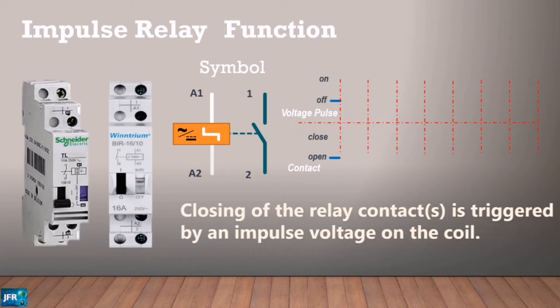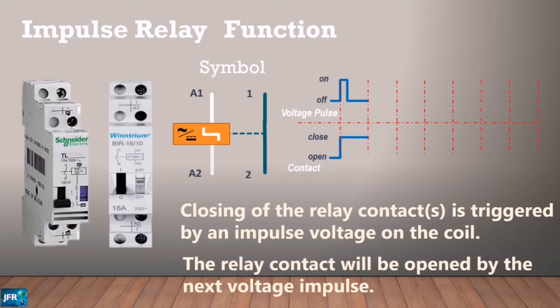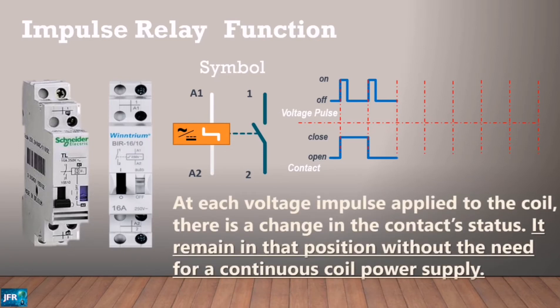Regarding impulse relay function: closing of the relay contacts is triggered by an impulse voltage on the coil. The closed relay contact will then be opened on the next voltage impulse. At each impulse voltage applied on the coil, there is a change in contact status, and it remains in that position without the need for a continuous coil power supply.